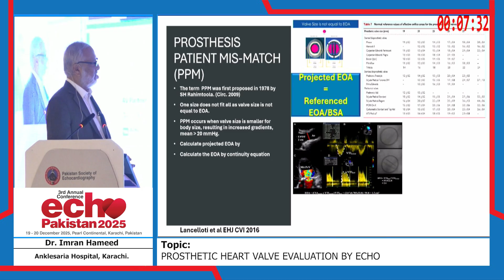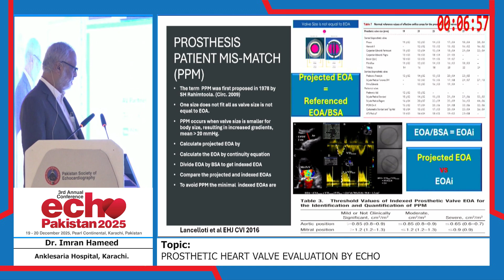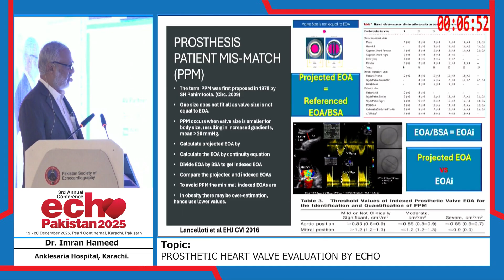Second, in your echo lab, when the patient has been implanted, you calculate effective orifice area by continuity equation, as already explained, and divide this effective orifice area by BSA to get indexed effective orifice area. Now you have the referenced effective orifice area and the indexed effective orifice area. So you compare these two, and if you get at aortic position greater than 0.85, at mitral position greater than 1.2, it's okay. But 0.65 and 0.9 means stenotic or thrombotic. For obesity, they have reduced these values to 0.55 and 0.75.